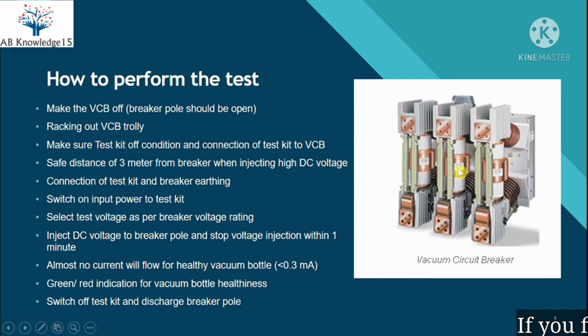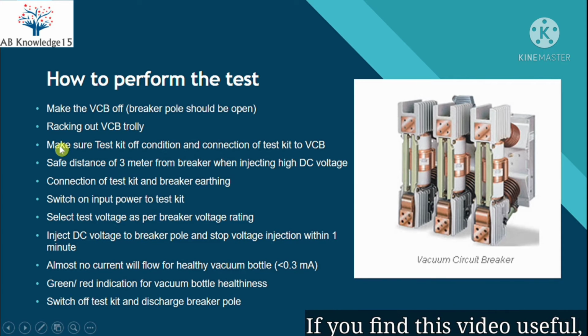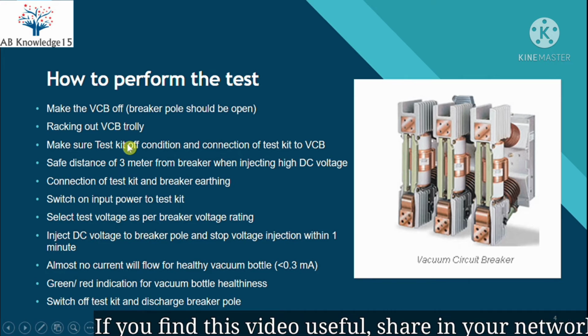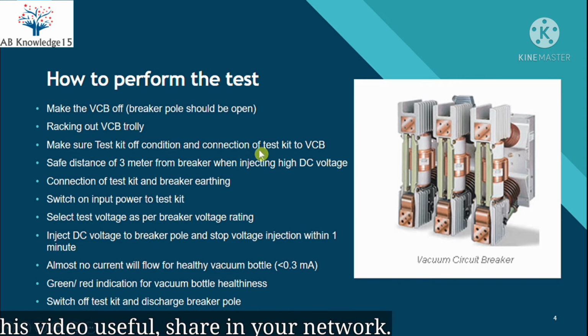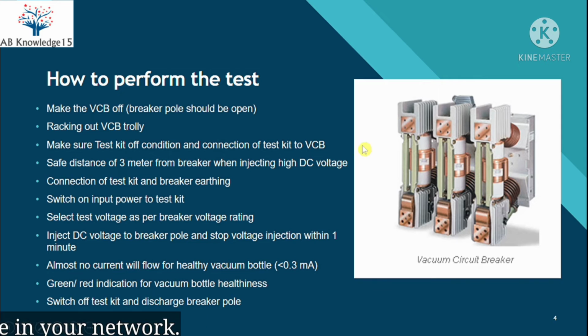Now, make sure that the test kit is in off condition and make the connection of the test kit to the VCB. Suppose you want to test this vacuum bottle. The test kit contains 2 probes for connection to the breaker pole. So connect the first probe to the first contact of the breaker and connect the second probe to the second pole of the breaker.